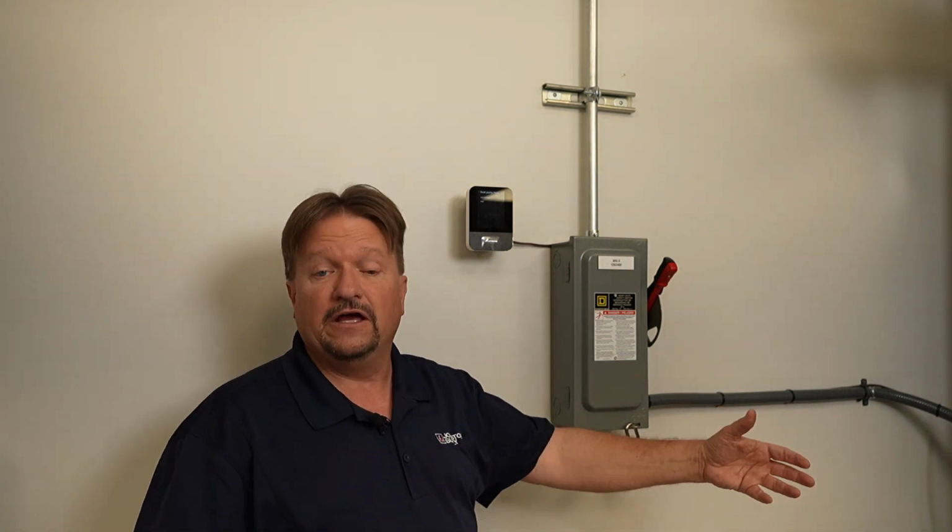If I don't see 7 on my superheat, then I've got something wrong, because this EEV has been tuned to run at 7. Now when I say my EEV, it will be the outdoor EEV, of course, because it's in heat mode. It should be tuned to 7 degrees Fahrenheit. So it is tuned to that.